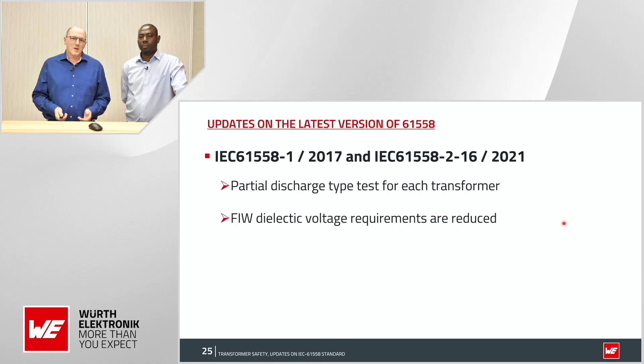The FIW dielectric voltage requirements are reduced now, and the clearance distance is calculated with the rated supply voltage. In the past, the clearance was also calculated with the working voltage.